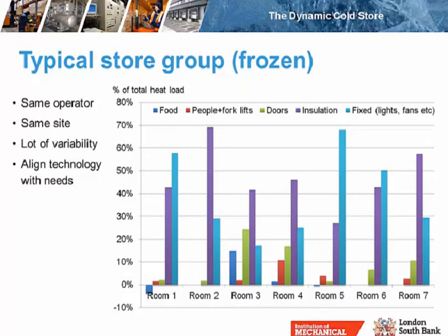I'm showing on the graph here seven different cold rooms — all from the same operator, on the same site — but you can see a lot of variability in the different heat loads: from food, people and forklifts, doors, insulation, and fixed heat loads from lights and fans. In room three, you have a high heat load from doors; infiltration is relatively high in room four. But in rooms one and two it's very low. So technologies that reduce infiltration might be very viable in rooms three and four, but would have little feasibility in rooms one and two.